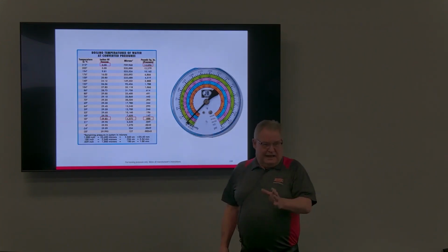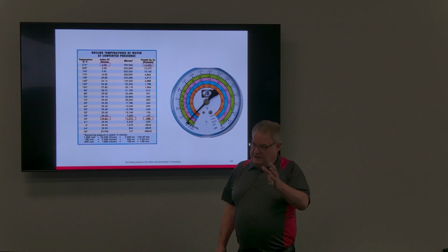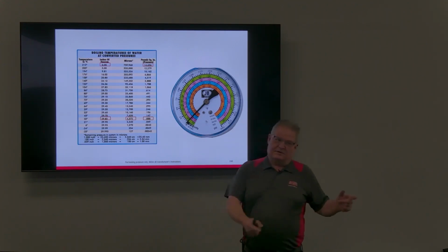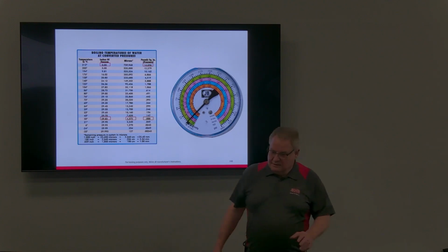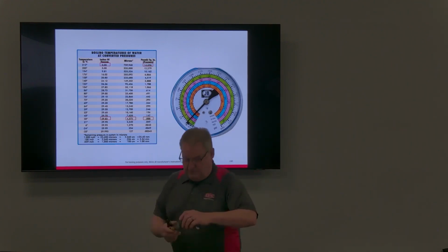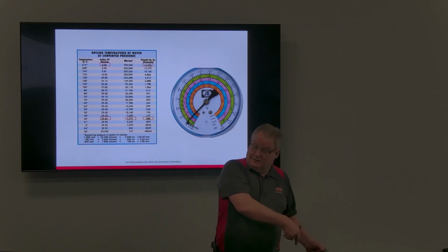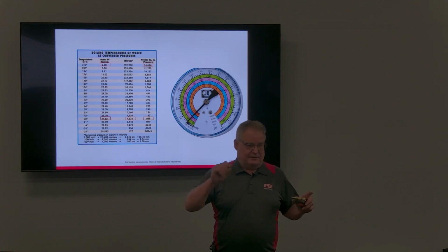I know they sell gauges with the micron gauge built into the gauge. I don't really care what the microns are at the gauge manifold. I care what the microns are at the unit. So ideally, your micron gauge should be at the unit itself. So anybody got that Navac pump with the micron gauge built into it?